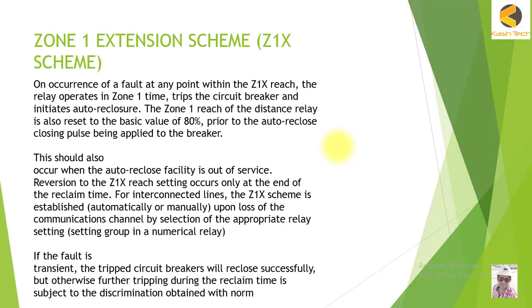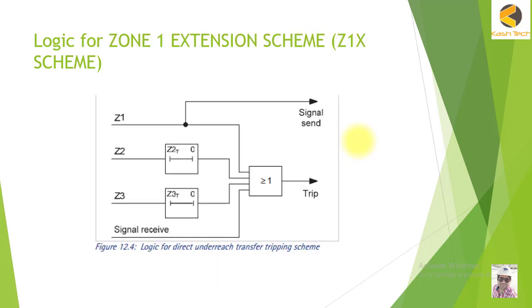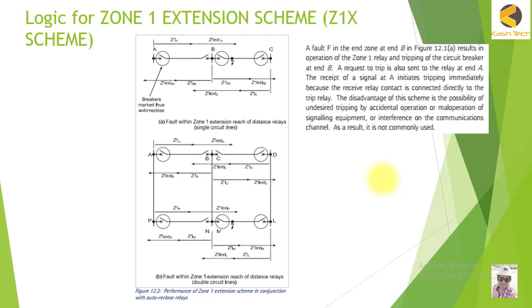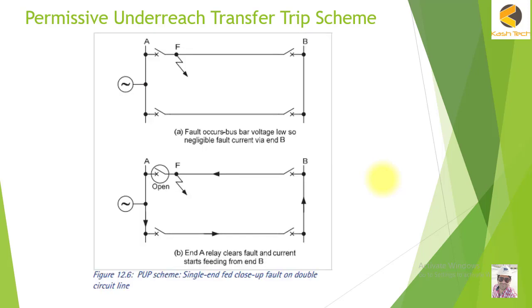After Zone 1 is extended, it is blocked again after a certain time. We will examine the different situations where this scheme is selected. We will also look at the logic in detail. Then we will understand the Permissive Underreach Transfer Trip (PUTT) scheme — this is the scheme I have seen most used in protection systems throughout my 17-year career. I will explain where to choose PUTT and where to choose Permissive Overreach Transfer Trip (POTT).